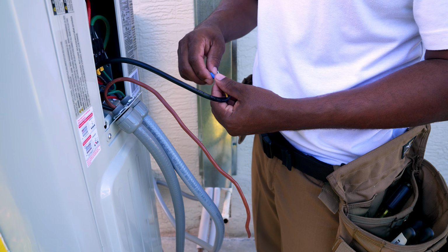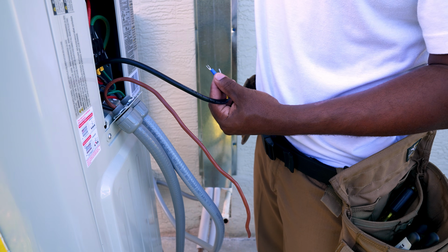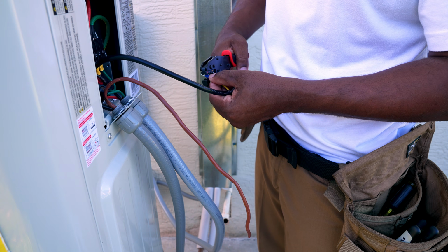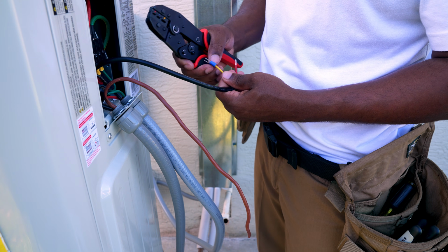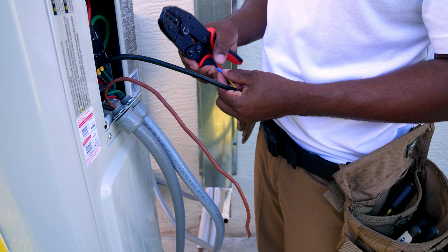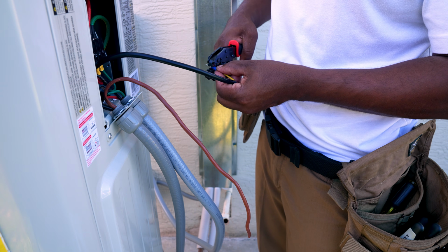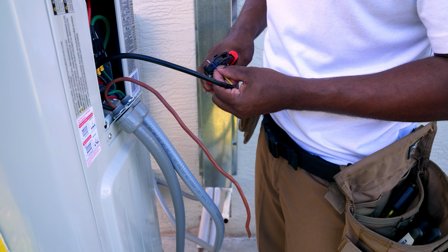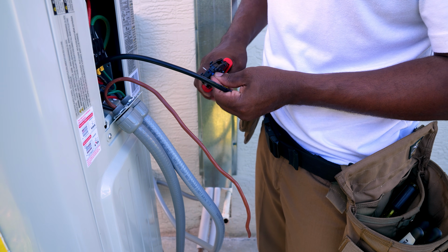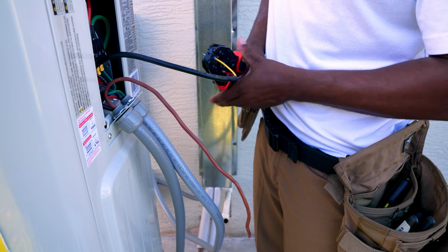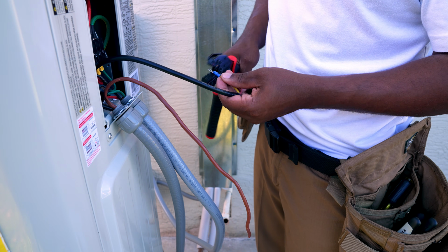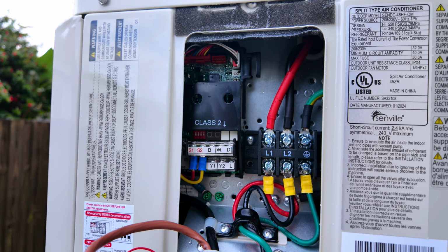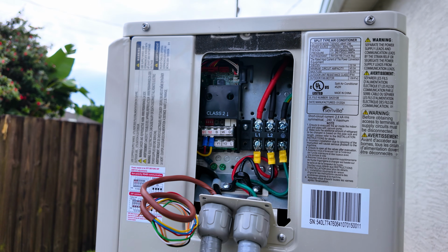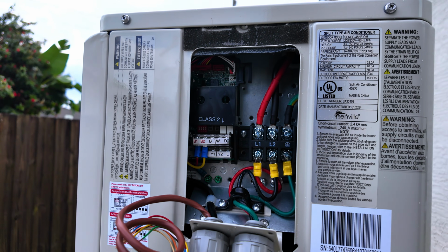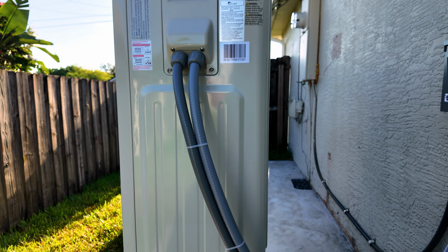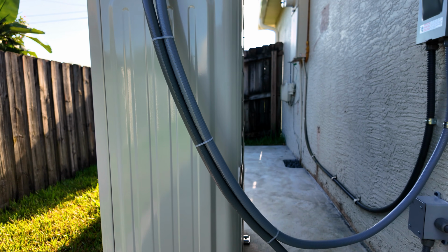I did the same thing for the S1 and S2 communication bus between the outdoor unit and the indoor unit. The reason why I have two wires here rather than one, the black wire is for the communication bus and the brown thermostat wire is for if you're using 24 volt thermostats. For example, I have a smart thermostat that I was using on the old unit. I may use that later, but I want to make sure that the proprietary one works just fine first.